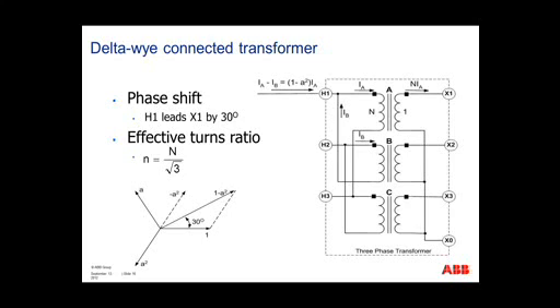For a Delta-wye connected transformer, here we have the Delta connected on the high side of the transformer. If we look at the connections here, instead of an A minus C connected Delta, we have an A minus B connected Delta, with H1 connected to the polarity mark of A and the non-polarity mark of B. H2 connected to the polarity mark of B and the non-polarity mark of C, and H3 connected to the polarity mark of C and the non-polarity mark of A, giving us an A minus B delta.